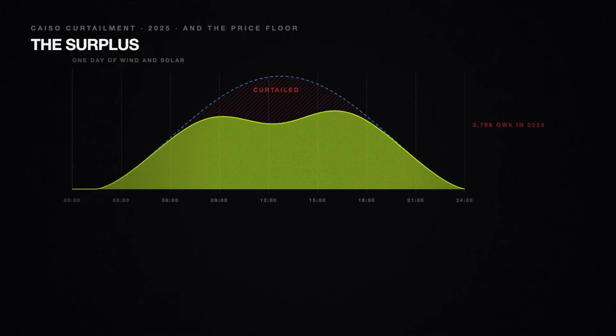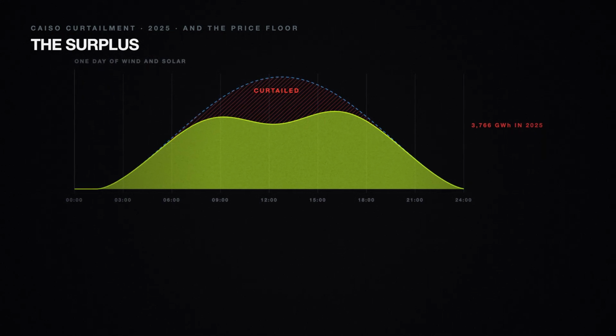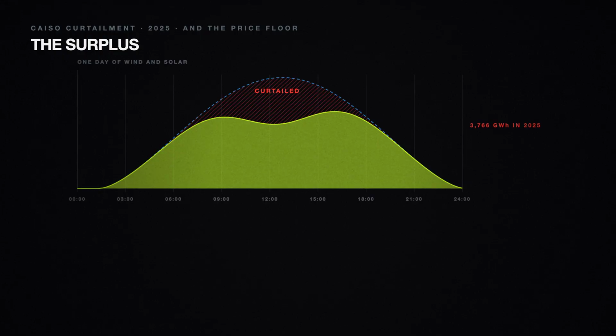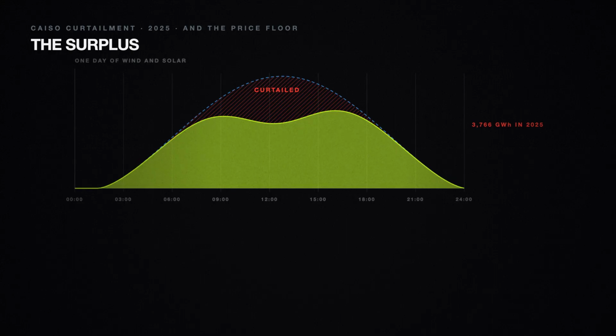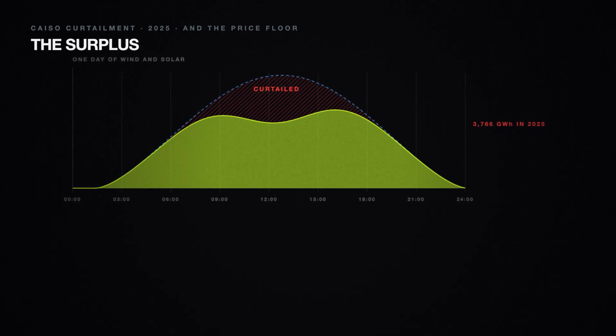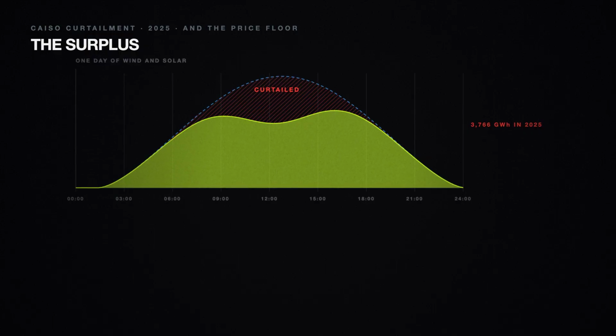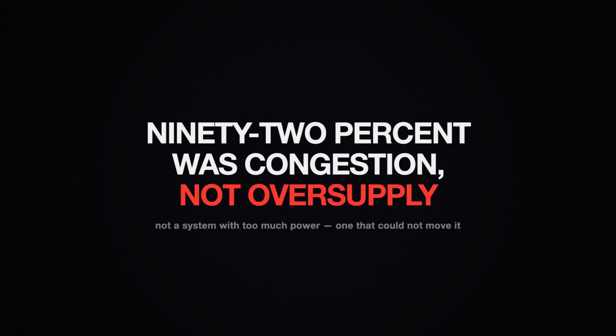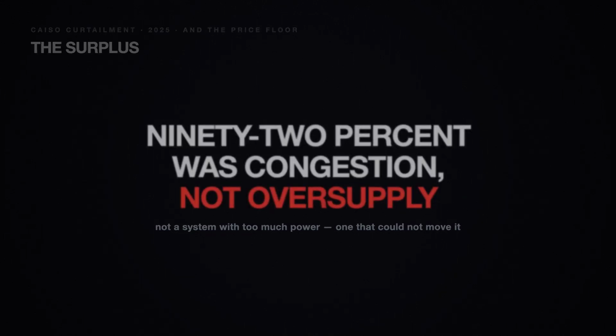Now turn the problem over, because a grid that cannot store power has a second failure mode, and it is the opposite one. Sometimes there is too much. In 2025, the California system operator curtailed 3,766 gigawatt-hours of wind and solar, power that existed, that cost nothing to produce, and that was deliberately not taken. The popular explanation is oversupply, too much solar at midday, nowhere to put it. The operator's own data says otherwise. 92% of curtailed energy was classed as local transmission congestion, not a system with too much power, a system that could not move it out of where it was.